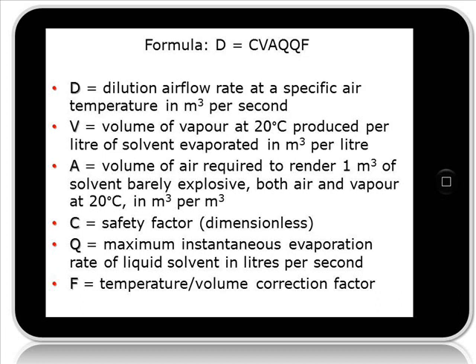Generally speaking, the common characteristics of common flammable liquids can be found in AS1375 Table G. Under the column heading 'air rendered barely explosive by one litre of liquid solvent in cubic metres,' that will give you the requirement for the VA component. C is a safety factor — depending on whether it is a continuous oven or a batch oven, you should decide which value to use. Q is the instantaneous evaporation rate of the liquid in litres per second, which you should be able to find out.